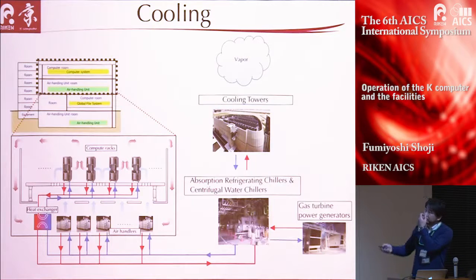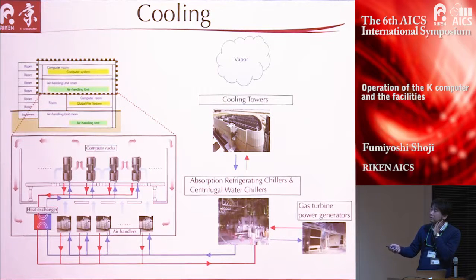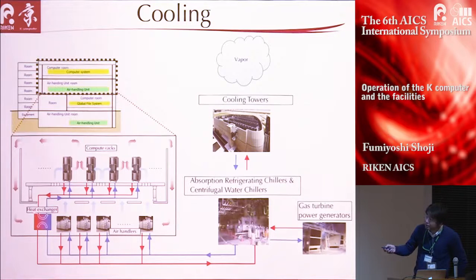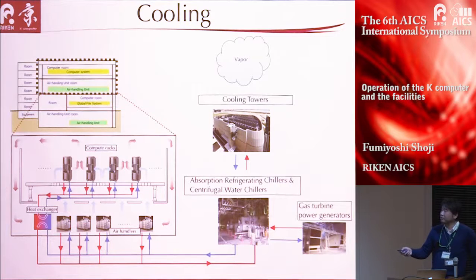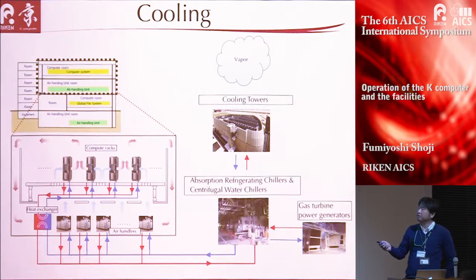This slide shows the cooling system as a cross-section view of the computer building. There are loops of air and loops of water. The water loop consists of two parts: one between the computer racks and the heat exchanger, and the other between the heat exchanger and the chillers. Energy consumed by the K-computer ultimately goes to the air from the cooling towers.